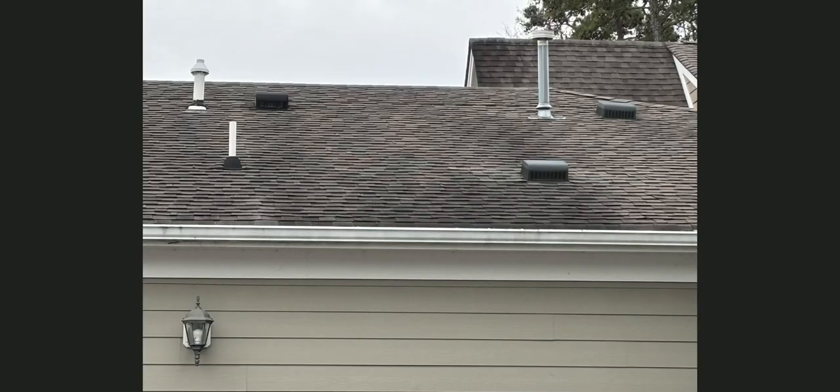Many believe that roof vents installed at multiple different heights will lead to short-circuiting. The thinking is that the upper exhaust vents will pull air in through vents that are near them, and this will cause reduced intake in the lower soffit vents. This thinking is incorrect due to a misunderstanding of the stack effect.